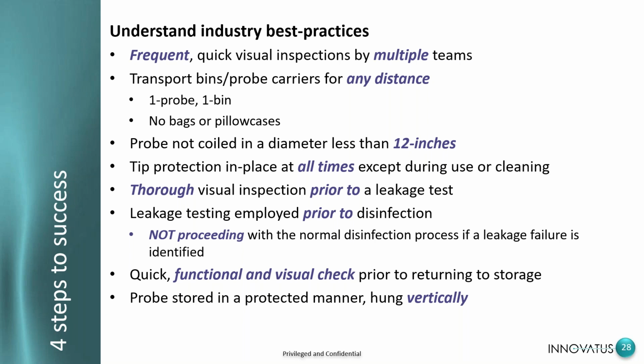So industry best practices, frequent and quick visual inspections by multiple teams. We always want to be looking at this probe because it is passing through so many different hands. Transport bins. Transport bins are critical. I'm seeing less and less pillowcases or red bags, blue bags, green bags. Not many people use the bags anymore, thankfully. Some years ago, I used to see probes being transported constantly in pillowcases, which pained me to no end. If we are using a transport bin, we want one probe per bin. Probe coiling, not coiled in a diameter less than 12 inches. If we coil it any tighter than that, that's okay for the main cable harness, but not okay for the insertion tube. If you coil it tighter, the insertion tube may develop a memory, or even worse, if we're coiling it too tight, you may end up kinking it.